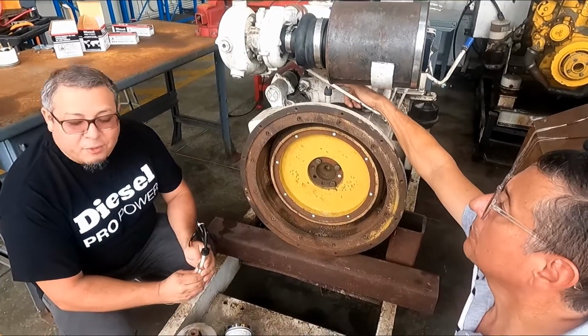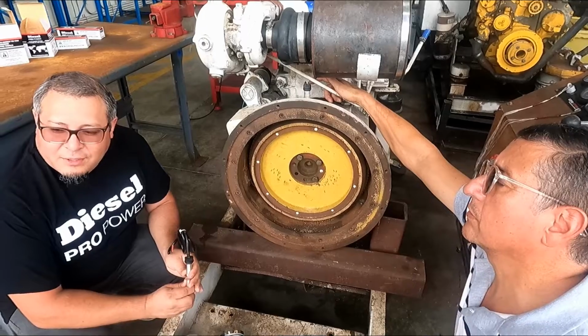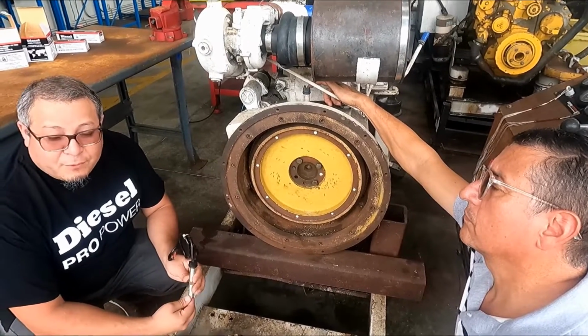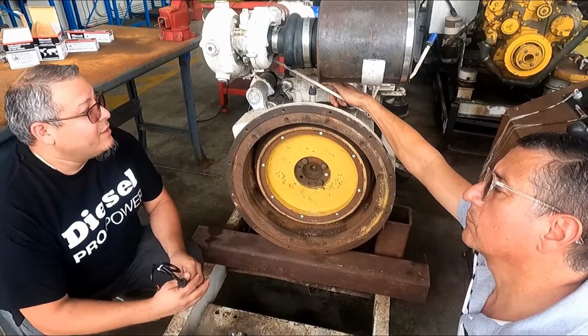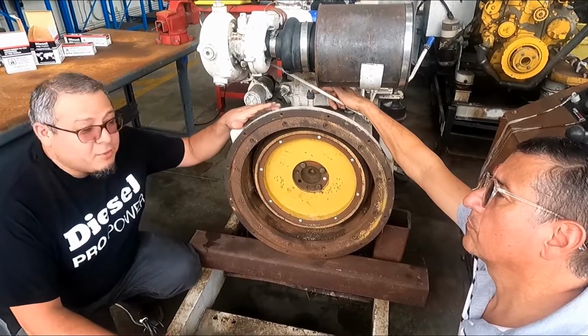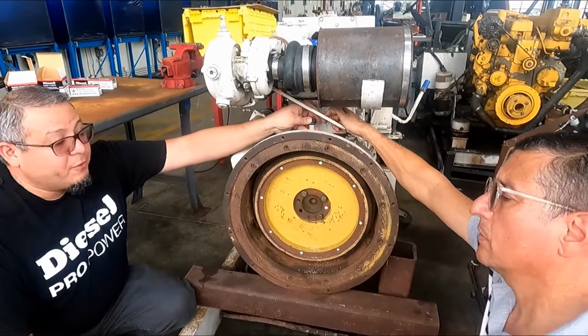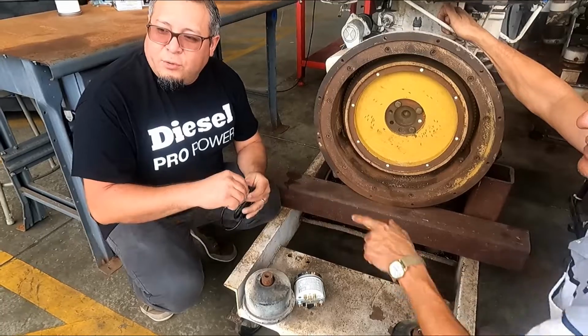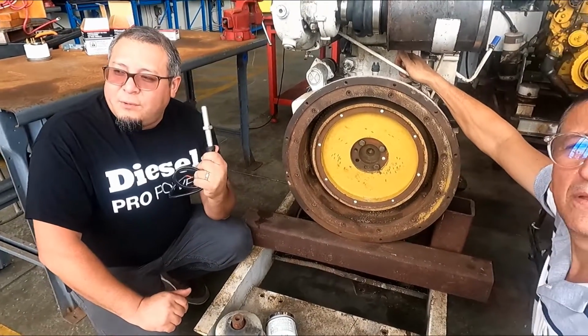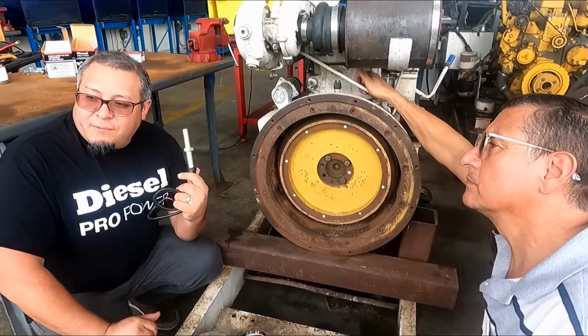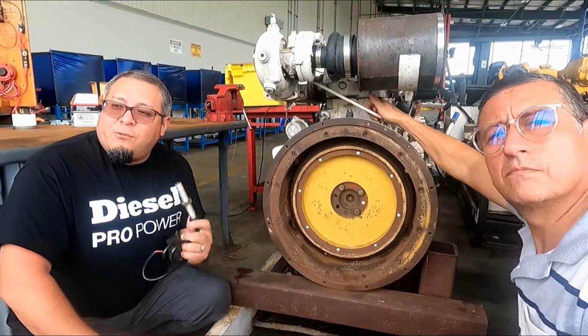On the bell housing — yes, all of them, even the 2-cycle engines, from the old 2-cycle engines to the new 4-cycle electronic engines — the flywheel housing will always have a magnetic hole for the magnetic pickup, which you bolt in. Typically, you'll have two different sizes: a 5/8 and a 3/4.